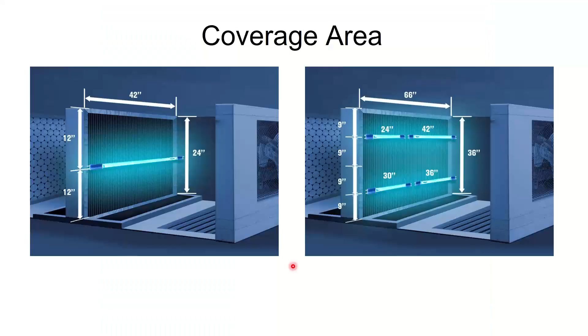So there's rules, and each manufacturer has charts for this kind of stuff on how much height a bulb can handle at how far a distance away. The further you put it away, the more height it can handle, but you only have so much room to work with, and then you're in the next section of the air handler, so that's not feasible either.